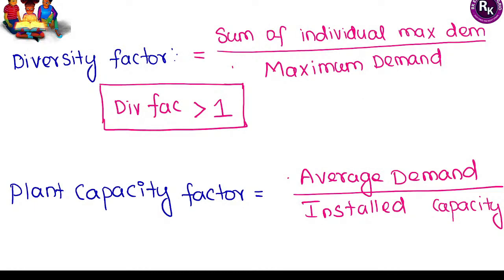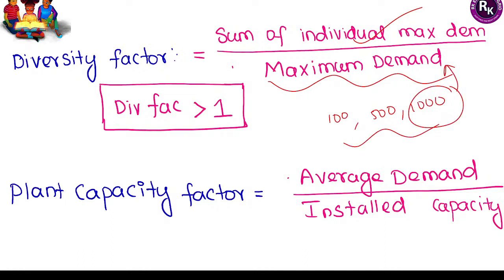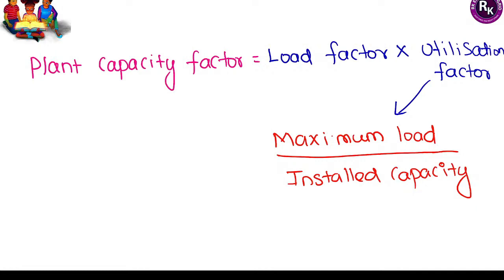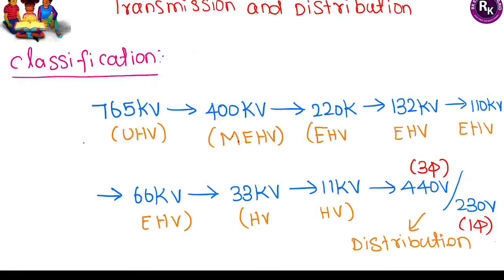Diversity factor is the sum of individual maximum demands divided by the maximum of those individual demands. Since the numerator is always higher than the denominator, diversity factor is always greater than one. Plant capacity factor is the average demand divided by installed capacity of the power plant. It can also be written as the product of load factor and utilization factor, where utilization factor equals maximum load divided by installed capacity.